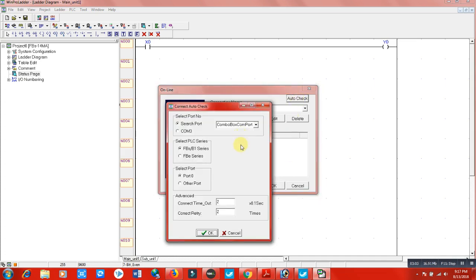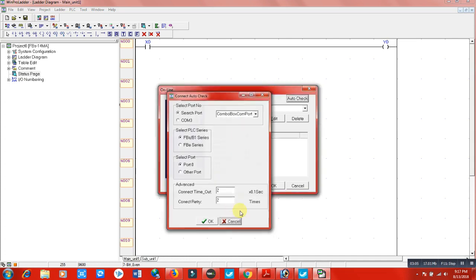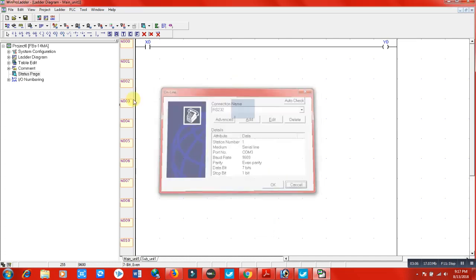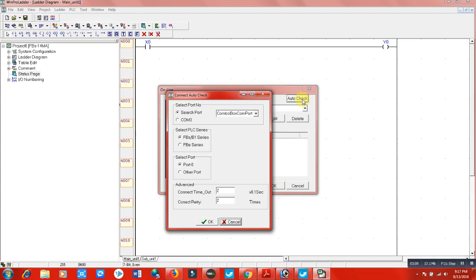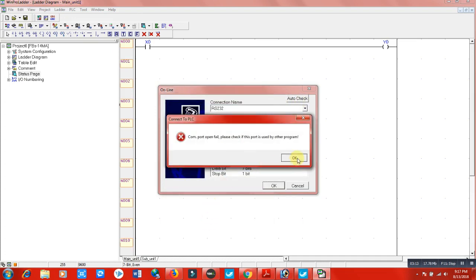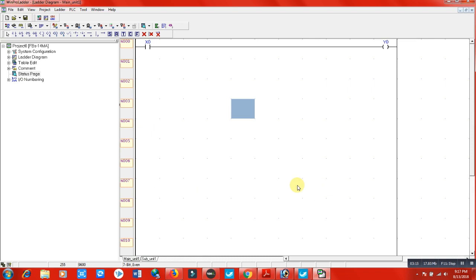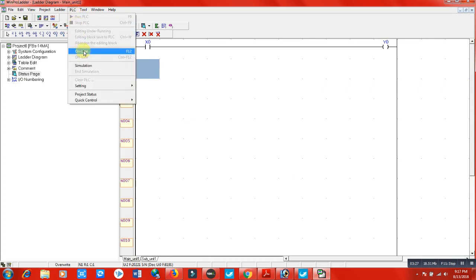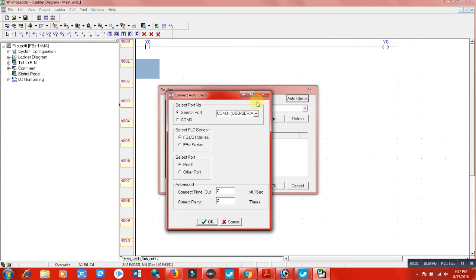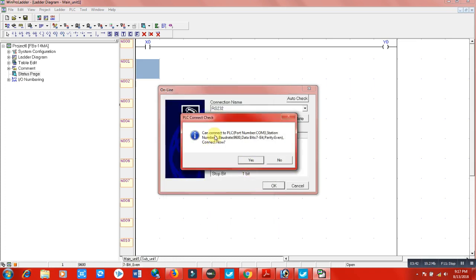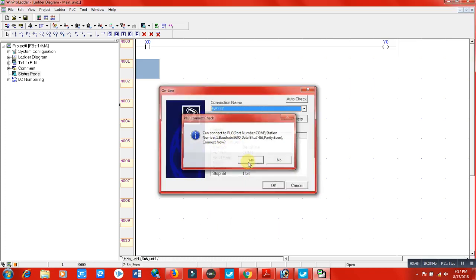Go to PLC, click online, click auto check. It is not working. Oh, I actually have not connected my PLC port, it's actually my mouse port. Go to PLC, click online, you have to click here auto check. When you click here it will show you in which port you have connected your PLC communication cable. As I have connected in COM port 3, click OK.